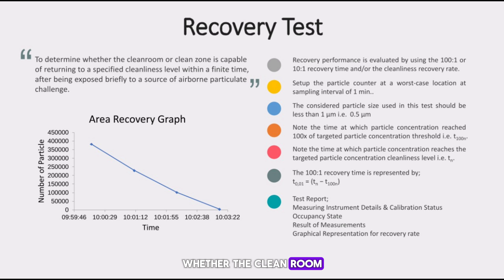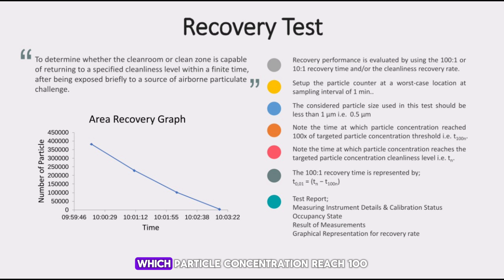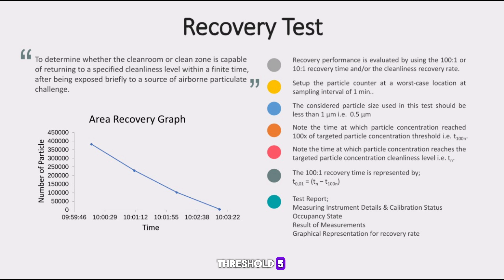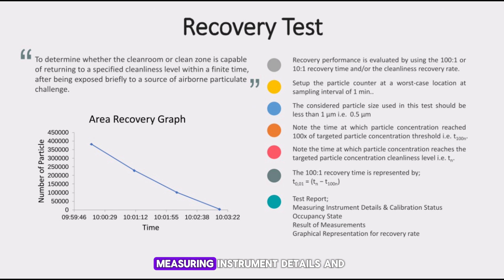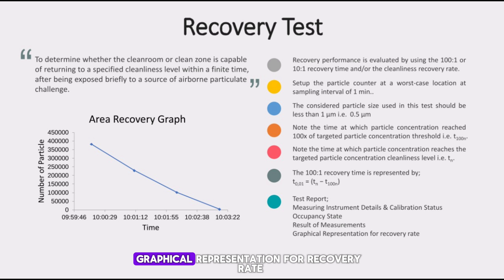Recovery Test — Purpose: to determine whether the cleanroom or clean zone is capable of returning to a specified cleanliness level within a finite time after being exposed briefly to a source of airborne particulate challenge. Key points: recovery performance is evaluated using the 100:1 or 10:1 recovery time or the cleanliness recovery rate; set up the particle counter at a worst-case location at a sampling interval of 1 minute; the considered particle size should be less than 1 micrometer; note the time at which particle concentration reaches 100× the targeted particle concentration threshold; note the time at which particle concentration reaches the targeted cleanliness level. Test report includes: measuring instrument details and calibration status, occupancy state, result of measurements, and graphical representation for recovery rate.